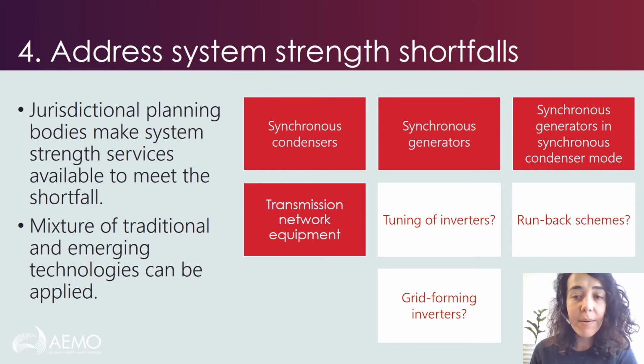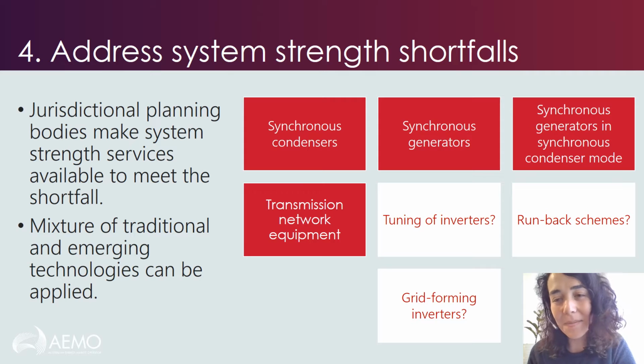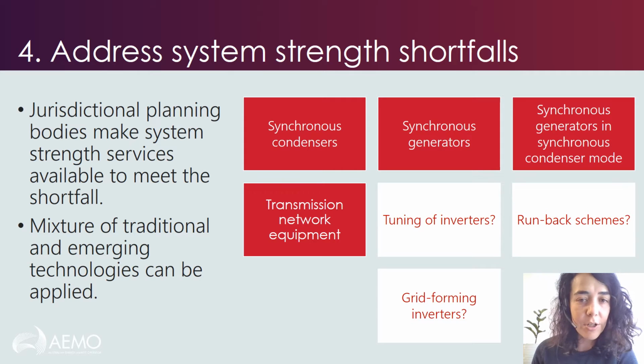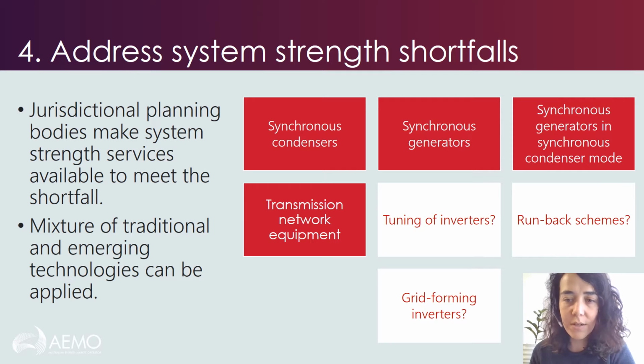Of course, PowerLink will have a range of options available to it to address the shortfall. I've listed here some of the options that we've seen in the past, so the use of synchronous condensers, synchronous generators in synchronous condenser mode, installation of transmission network equipment. However, because this is an emerging area of study, there are also other options such as tuning of inverters, run-back schemes, grid-forming inverters, which are emerging, and we expect this to be an area of strong technological innovation in the next couple of years as the industry as a whole adjusts to the new system strength situation.